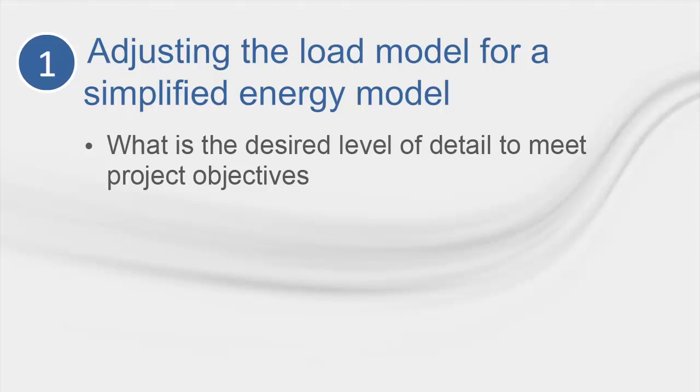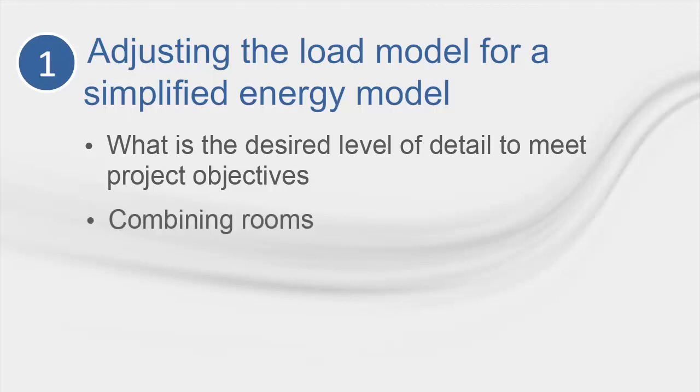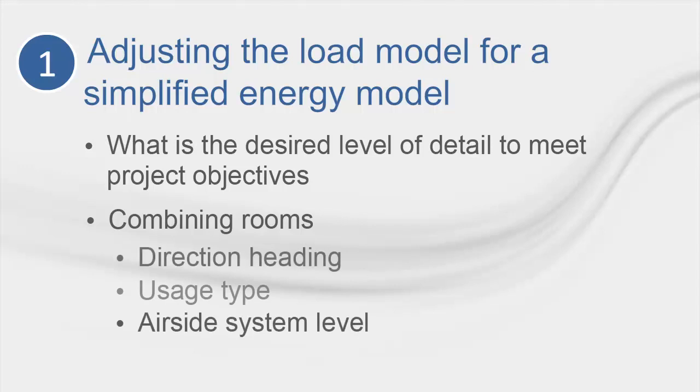Typically, load design requires a detailed, room-level model to verify proper equipment sizes and ensure ventilation requirements are met. However, energy models can generally be less granular, especially when they are being used for comparative purposes. For most users, the load-to-energy analysis adjustment will come in the form of building footprint redistribution, or zoning. For higher-level energy analysis, you may want to combine the zones based on directional facing.